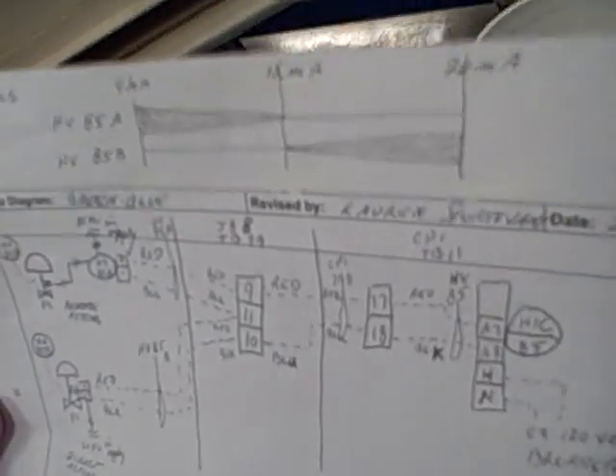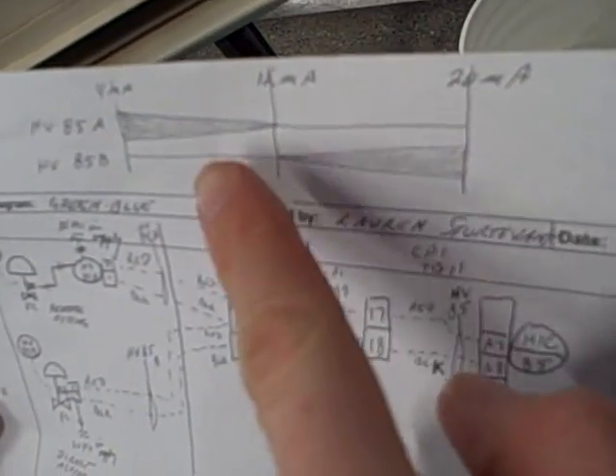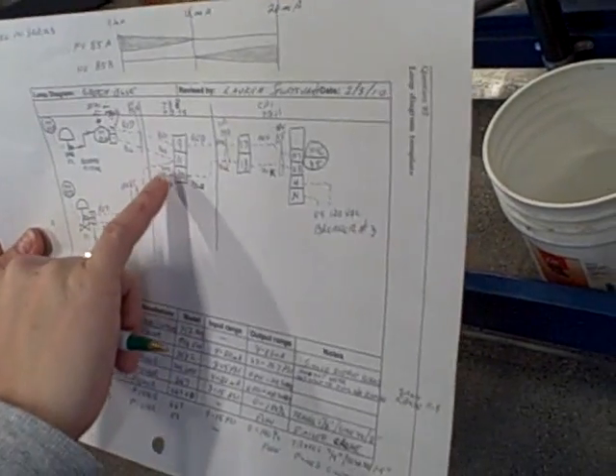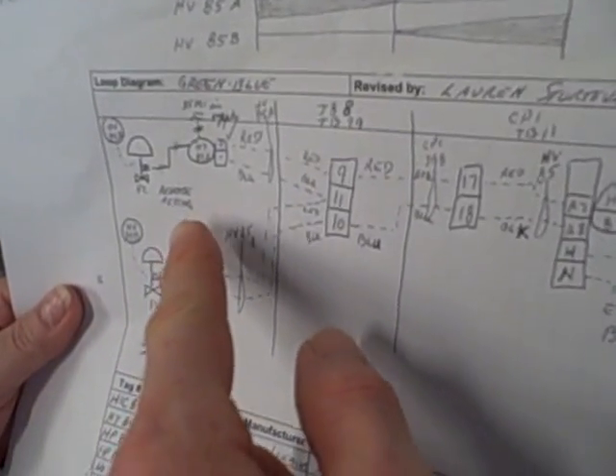And how are you denoting that on the diagram? See here, there we go. Lauren has the same sort of diagram. 4 milliamps, 12 and 20 with the triangle markings, HV85A, HV85B. Cool. I find that the clearest way to denote it by no means of standard. So it's right above. Cool. Cool. And that's direct acting and that's reverse acting. That's another way of showing.